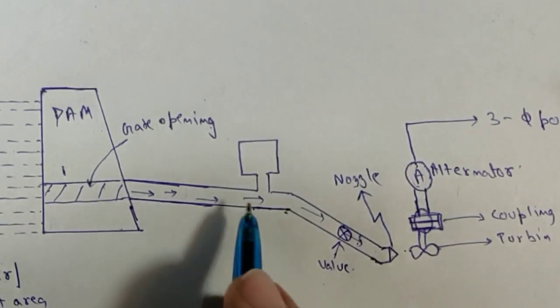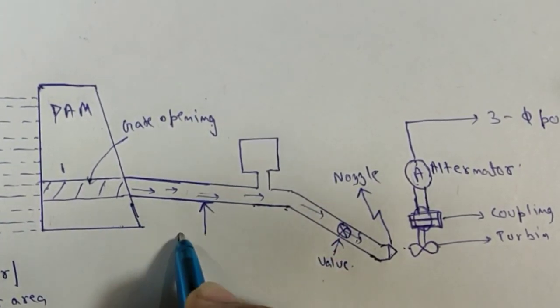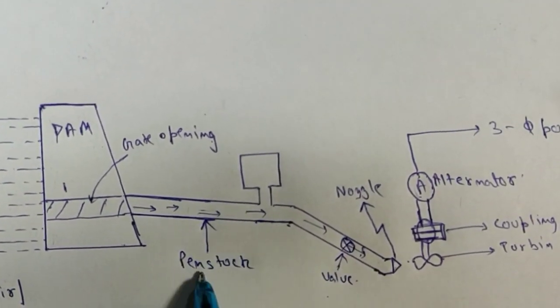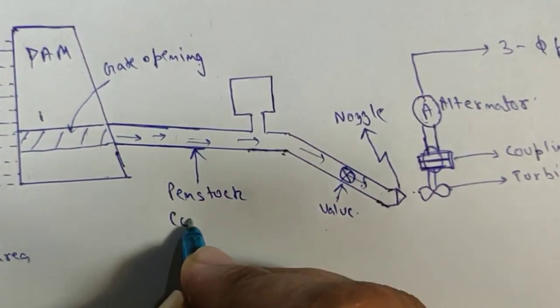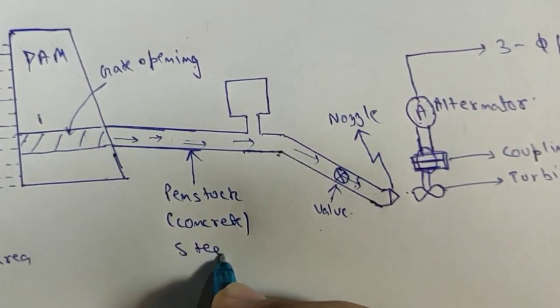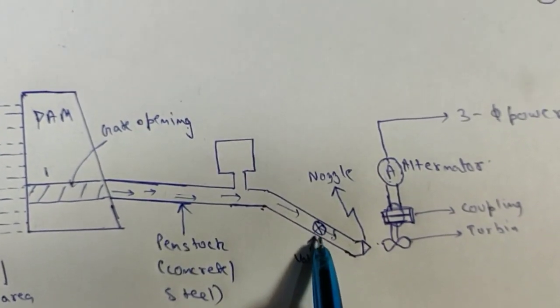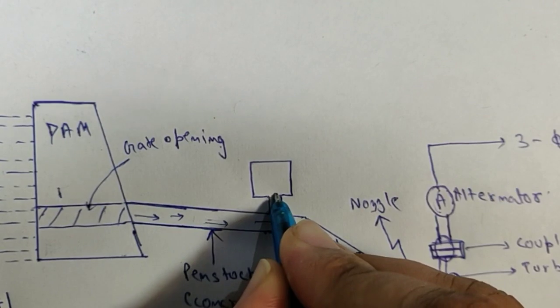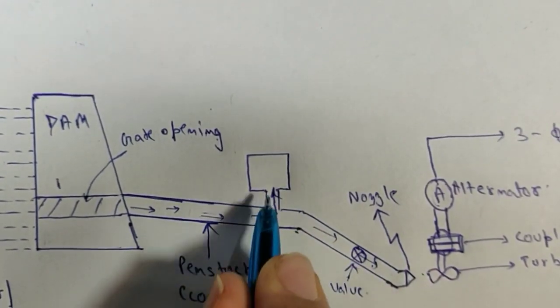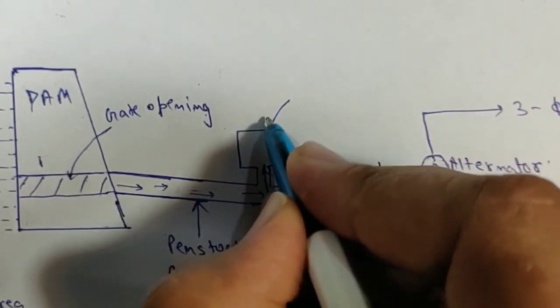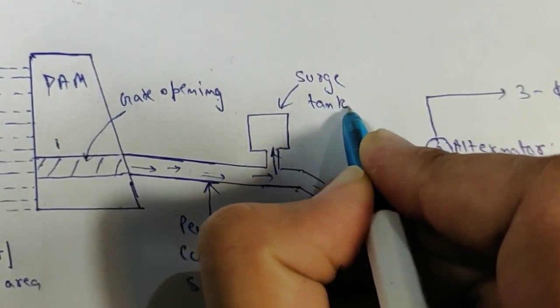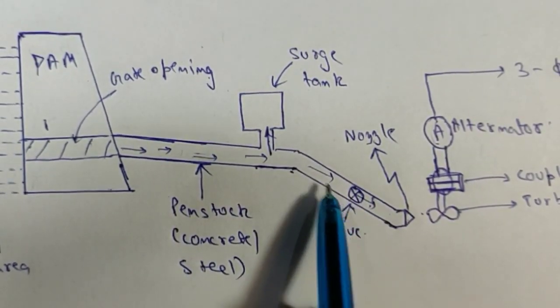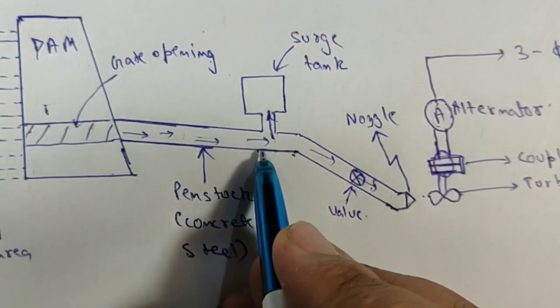Suppose I close the valve suddenly. Then the pressure in the pipeline — this pipeline is called our penstock, which is made of concrete or steel — increases very rapidly. This can damage the penstock. So to decrease the pressure when the valve is closed suddenly, we connect a surge tank. The basic function of the surge tank is to maintain the pressure in the penstock. When the valve is closed suddenly, some water flows into the surge tank so the pressure does not increase and the penstock is not damaged.